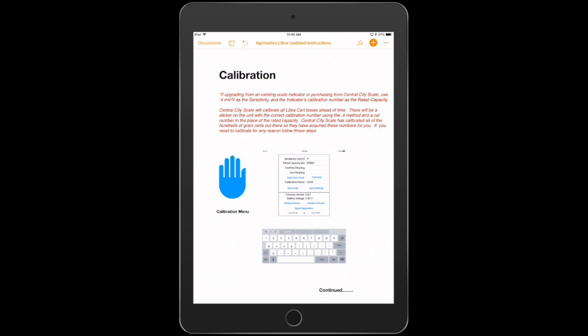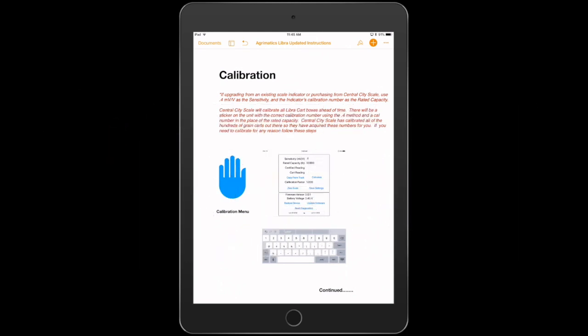We've simplified it so that you don't have to figure out what the sensitivity or the rated capacity are. We already have these numbers set up with previous scale heads, and so we've applied that same formula to the Libra to make it simpler just to go through and calibrate and do it on the fly. So if you always put in the 0.4 for the sensitivity, and then find your rated capacity, and we do have a chart. Let's say we have a 3-bar Weightronics. We would put in 36,900.